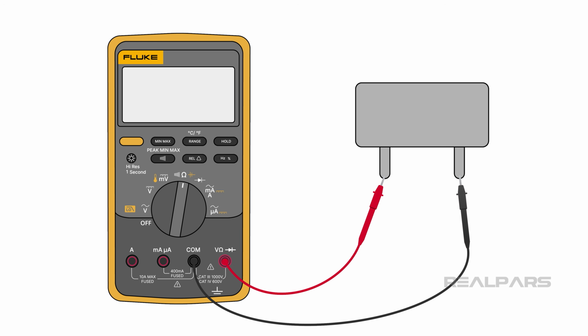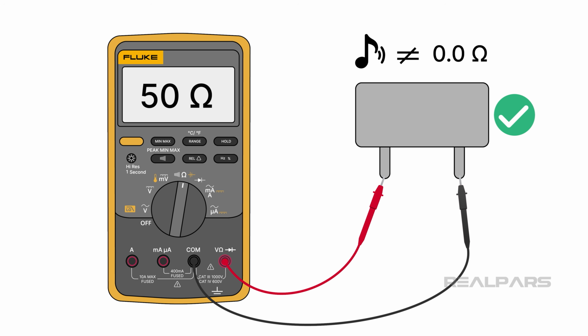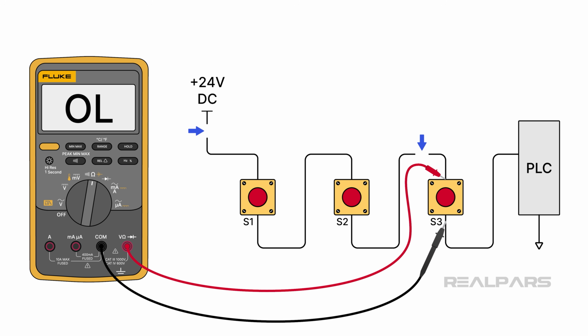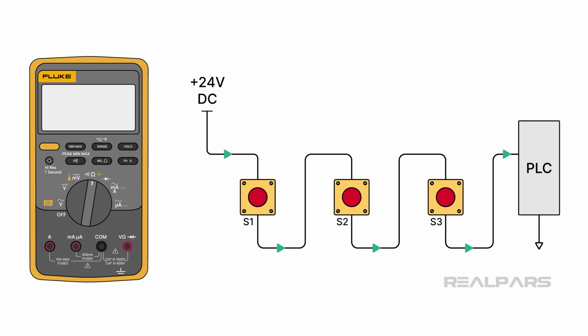As a point of caution for other continuity measurements, don't assume the beep indicates a 0 ohm condition, as many DMMs will produce a beep even if the measured resistance is as high as 50 ohms. If you rely only on the beep, you might incorrectly assume a device under test is functioning properly when it actually has higher resistance than you conclude, leading you away from the real issue. At the end of the day, regardless of how smart your PLC is, traditional skills in voltage, resistance, and continuity measurement are an asset for locating the defective switch or wiring fault.